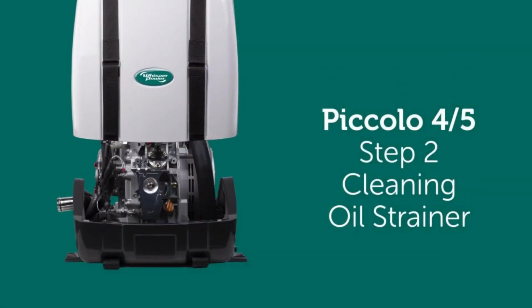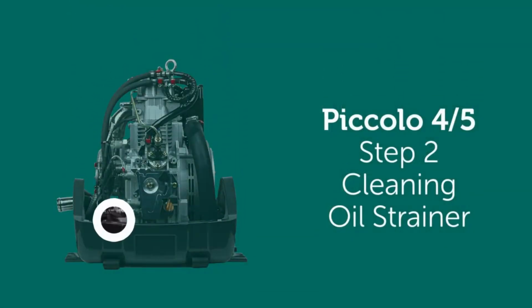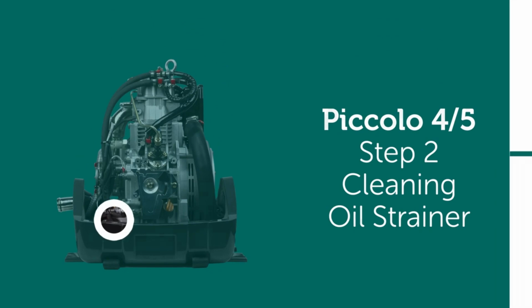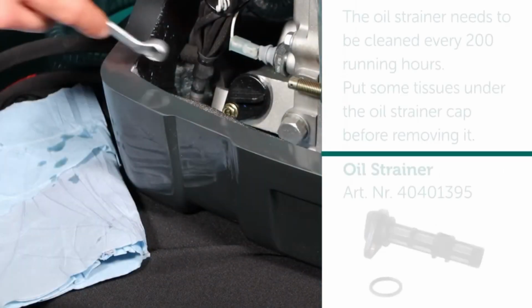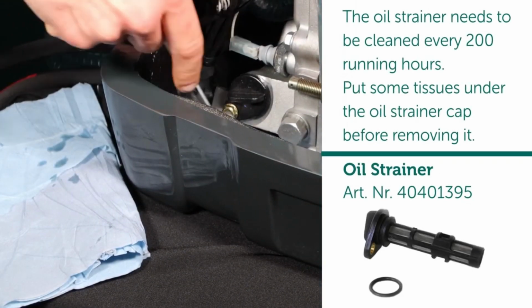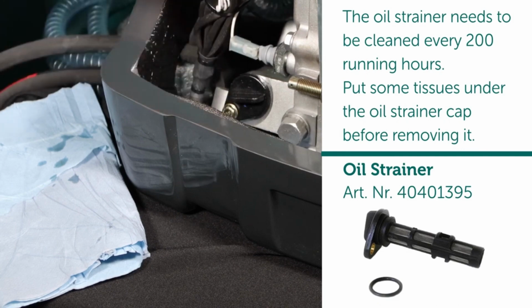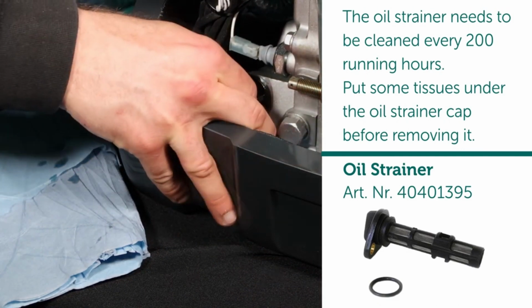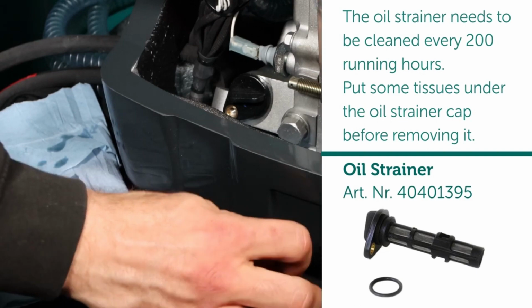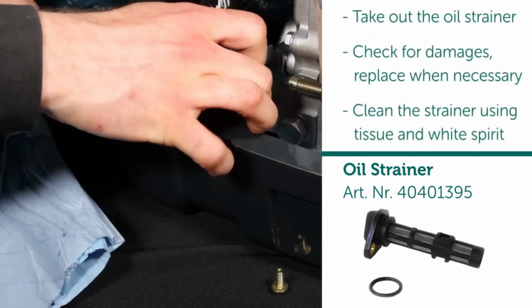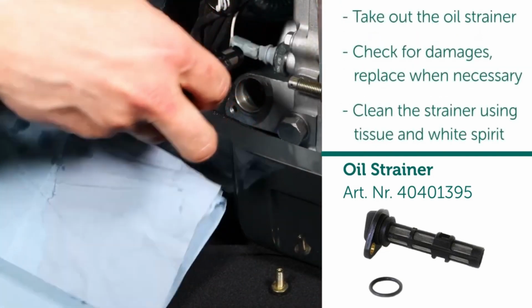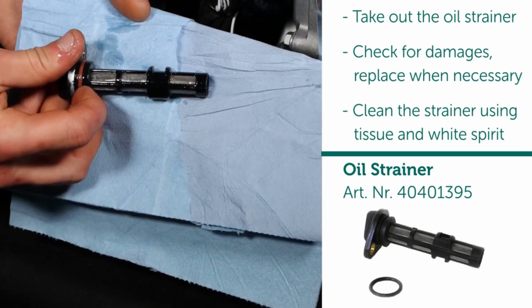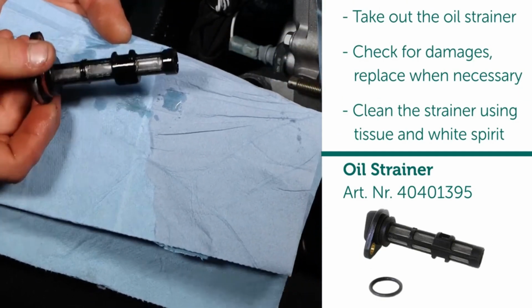Step 2. Cleaning oil strainer. The oil strainer needs to be cleaned every 200 running hours. Put some tissues under the oil strainer cap before removing it. Take out the oil strainer. Check for damages, replace when necessary. Clean the strainer using tissue and white spirit.